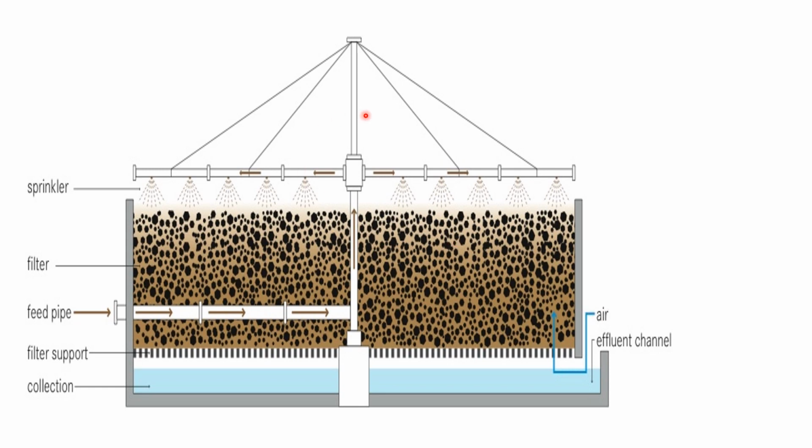Okay, this is the working of trickling filter. Actually, we allow the sewage water to enter through this inlet. It moves upwards as this rotating distributor rotates. These two side arms also rotate, and this sewage water reaches into these two side arms. It uniformly falls down to the filtering medium through the sprinklers, and sewage water moves downwards through the filtering medium. As it moves downwards, the aerobic bacteria present inside the filtering medium carry out the aerobic oxidation of sewage water, and the treated sewage water is collected from the effluent channel. This is the working of trickling filter.